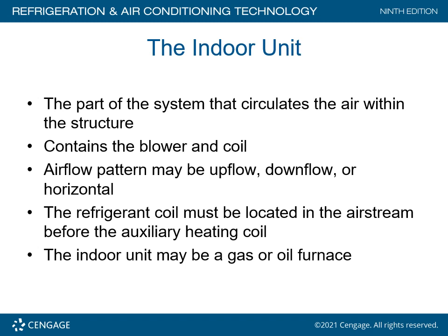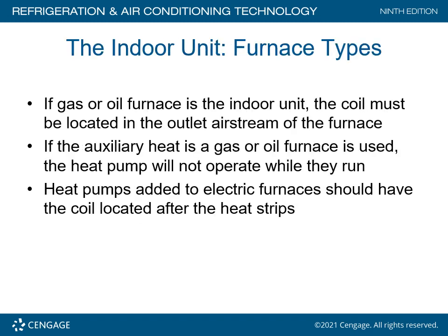The indoor unit may be a gas or oil furnace. If it's a gas or oil furnace that's utilized in the indoor section, the coil must be located on the outlet airstream of the furnace. If the auxiliary heat is a gas or oil furnace, the heat pump will not operate while they run. The heat pump added to an electric furnace should have the coil located after the heat strips.